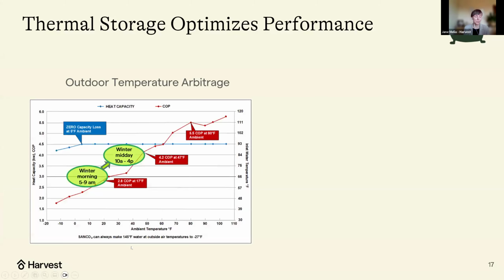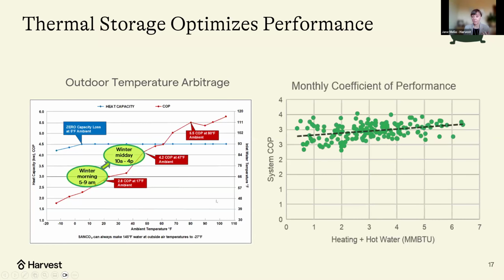So I mentioned a couple of times that heat pumps are temperature sensitive, and this chart is really trying to illustrate that. Horizontally, you can see the outdoor temperature, and the red line shows how the performance or efficiency of the heat pump varies with the outdoor temperature. So if you can choose to run your heat pump at noon rather than at 5 a.m. or 1 a.m., you can gain about a point of COP, substantially in terms of performance. And that's why harvest systems in the field have performance of 3 or 3.1 COP, 310%, which is a really strong performance, enabled by this temperature arbitrage that we're able to do.